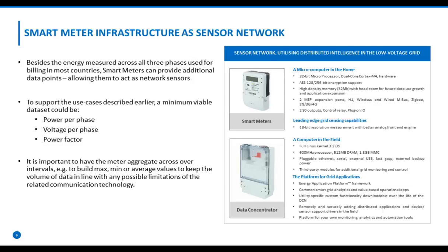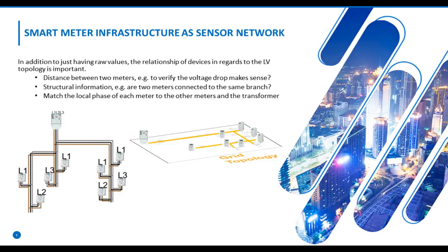We had already previous webinars, so we can present what we do. One thing is that the DC-13000 we have featured here is a computer, more or less, sitting at a substation and measuring the power line communication between meters to build a topology which is derived from the signal characteristics and the communication patterns. This topology, which I will show you on the next slide, is then used to build a logical model of the grid.